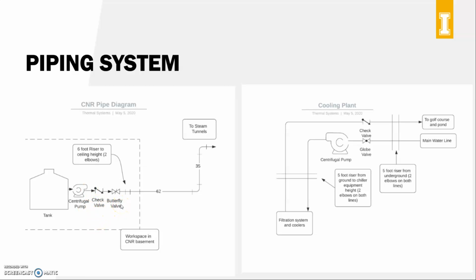And then next, we also have a butterfly valve. And this butterfly valve is so that if a maintenance worker needs to do work on the piping system or something, they can shut off the flow. Now, next it goes through a 6-foot riser, and because this is a 2D diagram, I don't have a way of representing that in 2 dimensions because this is in a 3rd dimension. So these lines are going to represent our riser, and it's a 6-foot riser, and it comes from the 6 inches off the floor up to 6'6", where it's overhead, and then it can travel through the rest of the room. It travels about 100 feet, and that's where it meets the steam tunnels, and I'll talk a little bit more about that in a minute.